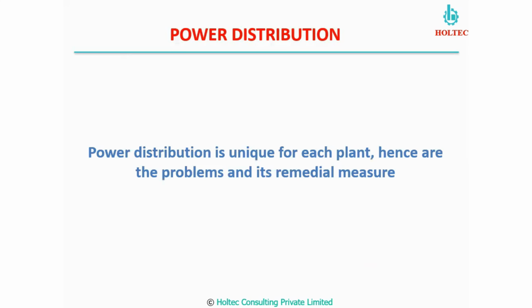The power distribution system is unique for each plant, hence the problem and its remedial measure. What it means is that you cannot make a prototype ILMS system. When we design an ILMS system, it should be unique for every plant. We cannot copy and paste one system which is running in one plant to another. One plant's requirement is not the same as another's. So there is a uniqueness, and we have to have a specific design for your complex power distribution system, your ILMS system.